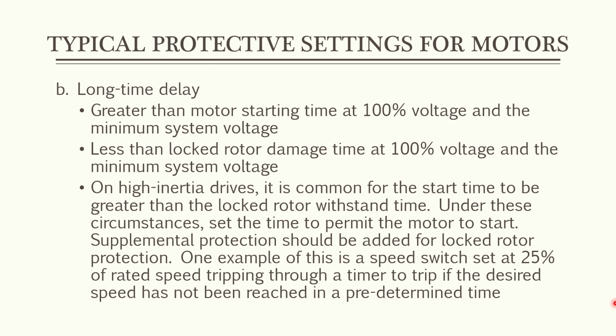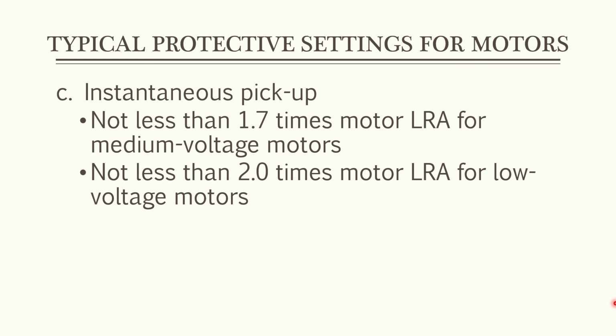On high inertia drives, it is common for the start time to be greater than the locked rotor withstand time. Under these circumstances, set the time to permit the motor to start. Supplemental protection should be added for locked rotor protection. One example of this is a speed switch set at 25% of rated speed, operating through a timer to trip if the desired speed has not been reached in a predetermined time. Next, we have the instantaneous pickup, not less than 1.7 times motor LRA for medium voltage motors, not less than 2.0 times motor LRA for low voltage motors.